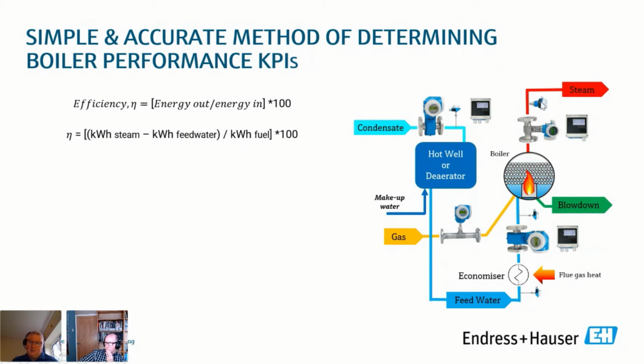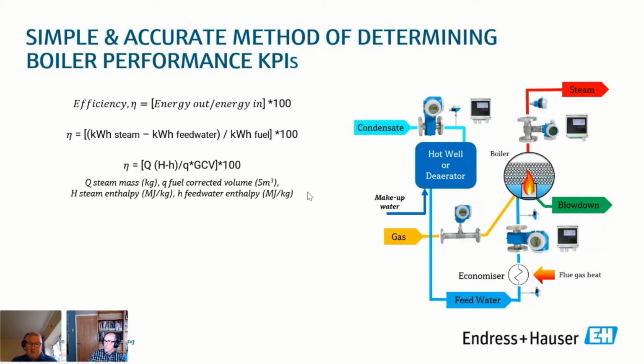But if we get the heat in the steam and we take away the heat that we're adding in the feed water, again, most people don't have meters on the feed water. So if you did, you can really account for what's happening with the blowdown and with the preheating of the feed water. But we can obtain the net heat then really simply by just taking away that feed water heat, and then we divide that by the energy in the fuel. And again, that's paying attention to the units, the corrected volume units, corrected to 15 degrees C. And if we do that, it's a very simple calculation.